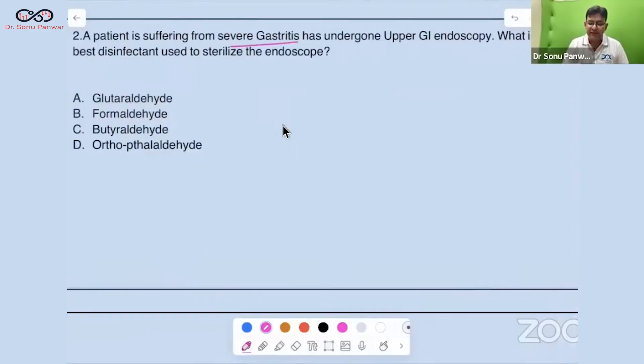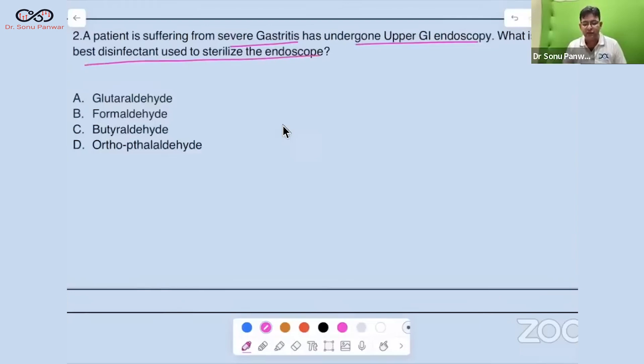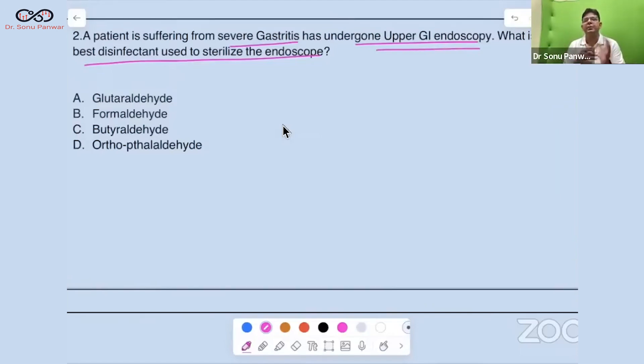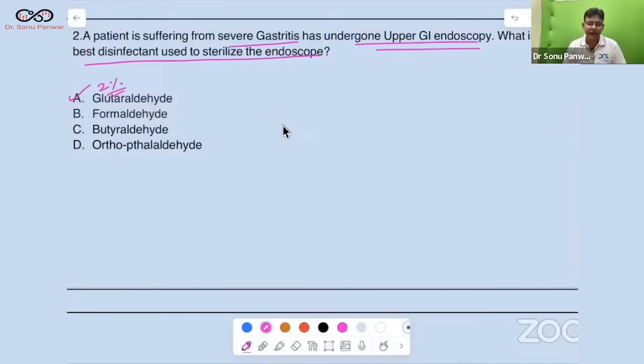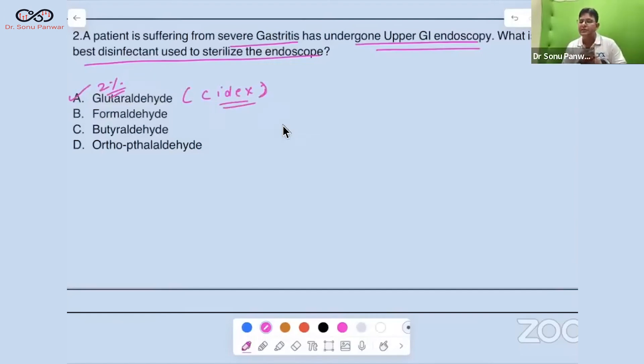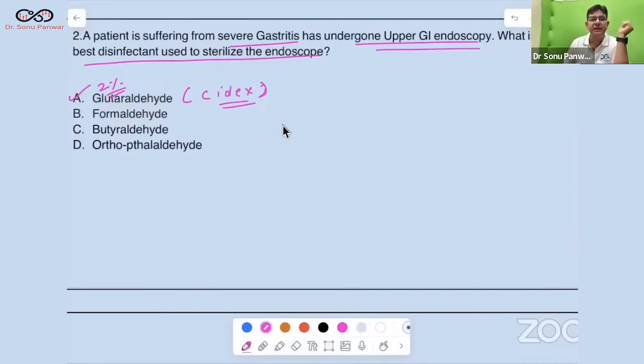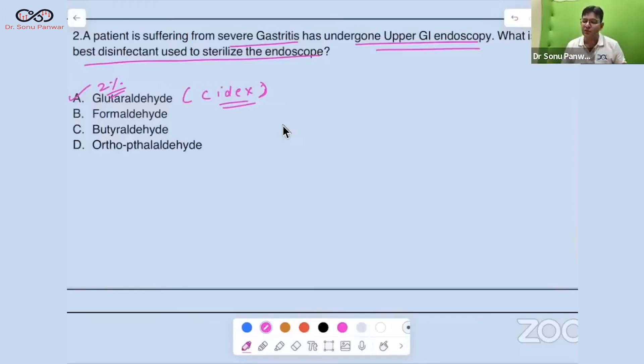A patient suffering from severe gastritis has undergone upper GI endoscopy. What is the best disinfectant to sterilize the endoscope? For costly instruments like endoscopes and bronchoscopes — worth around 10 lakh rupees — you should use two percent glutaraldehyde, which comes in the market by the name Cidex. This is used for all scopes.